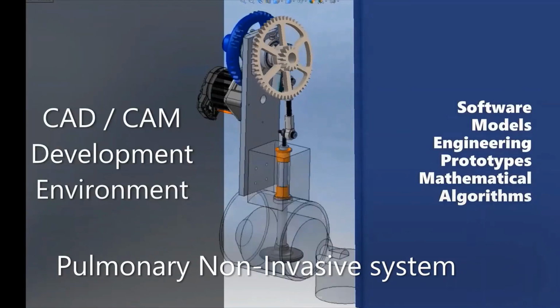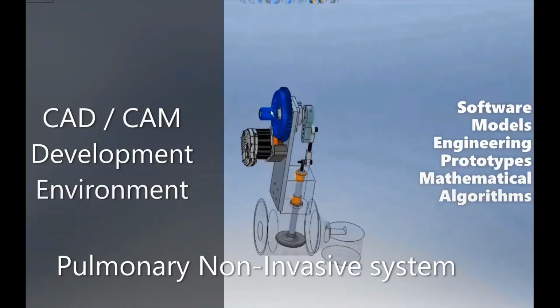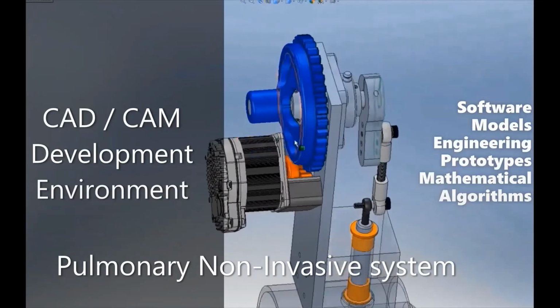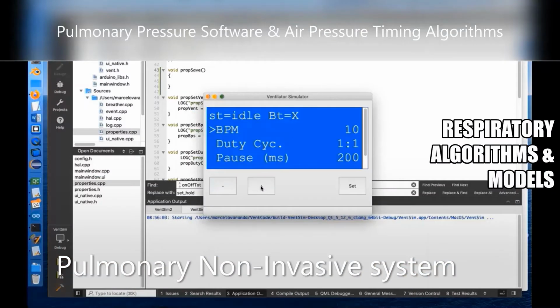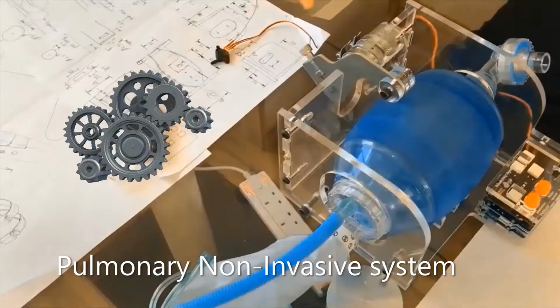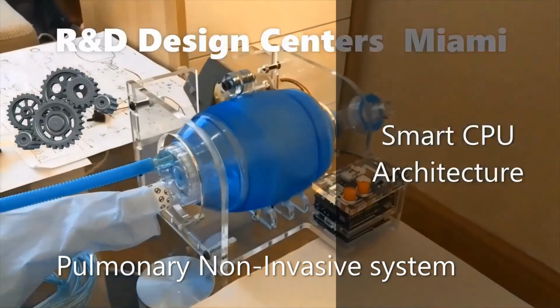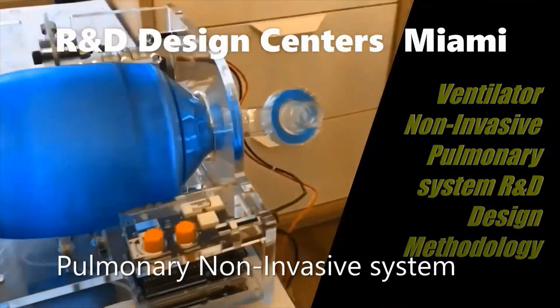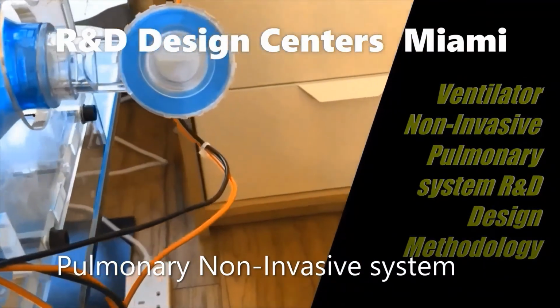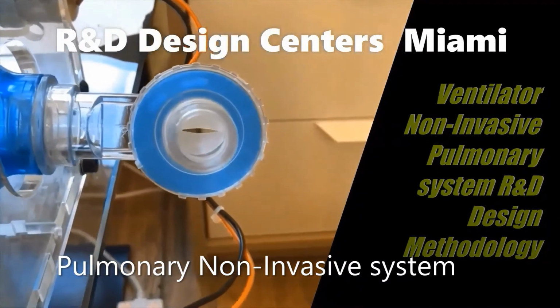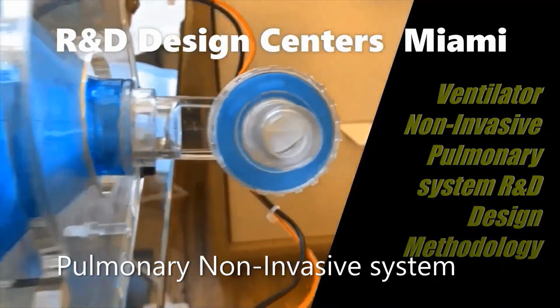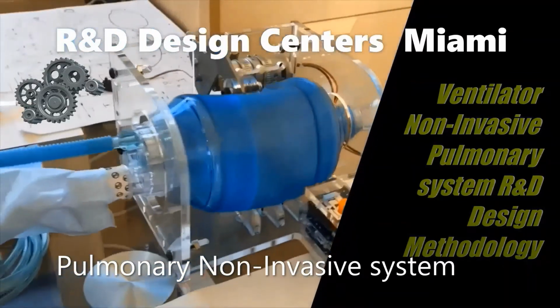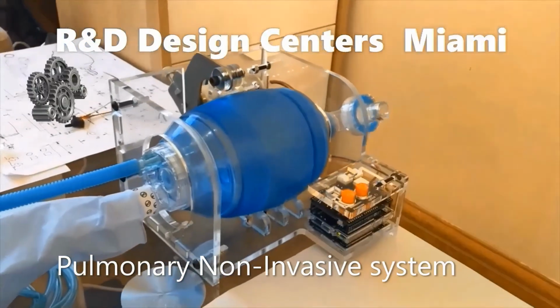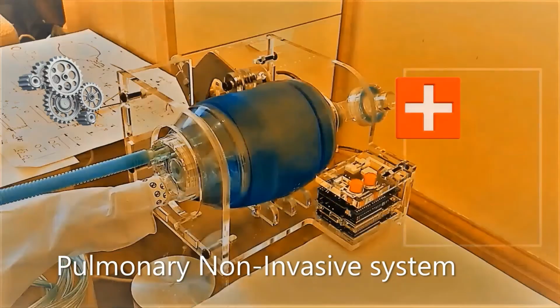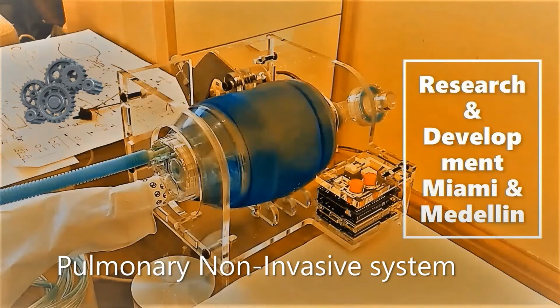The ventilator has a flow valve adjusting pressure to meet patient-specific parameters. When overpressure is released, the patient will exhale passively due to the lungs' elasticity. The exhausted air is released usually through a one-way valve within the patient circuit called the patient manifold.